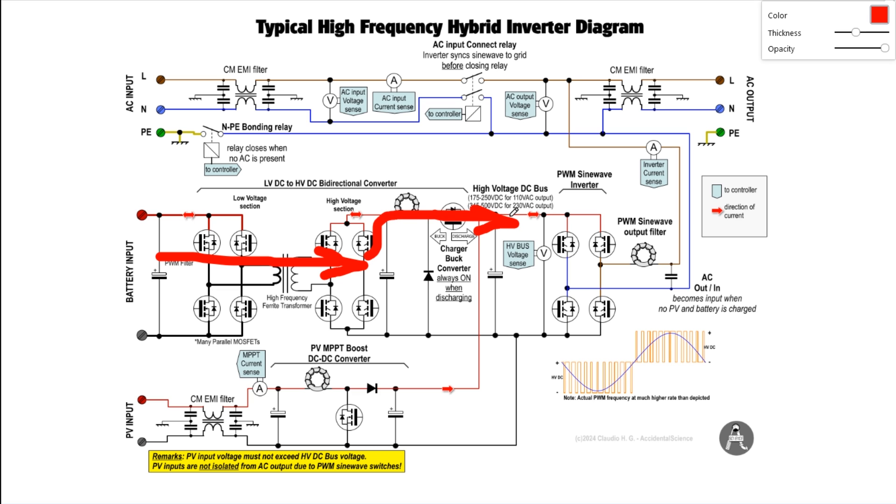And here a couple of important considerations. Because here we have only a boost converter, the input from the photovoltaic string must never exceed the maximum voltage of the DC high voltage DC bus here. And another important point is that the input of the photovoltaic is not isolated in respect to the high voltage bus and this has important implications as we will see soon.